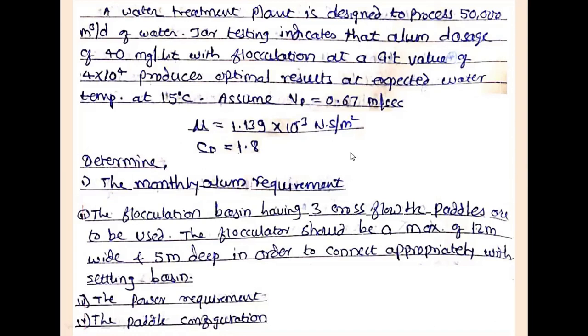Mu, the dynamic viscosity, is given as 1.139 × 10⁻³ Newton-seconds per meter squared. Cd is equal to 1.8. We need to determine: first, the monthly alum requirement; second, the flocculation basin having three cross-flow horizontal paddles; the flocculator should be a maximum of 12 meters wide and 5 meters deep to connect with the settling basin; and the power requirement and paddle configuration.